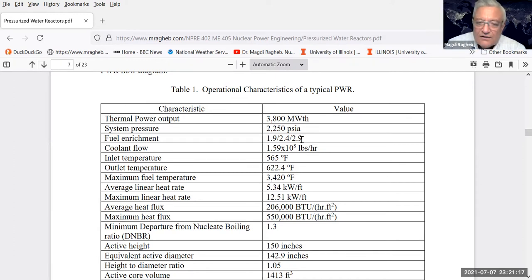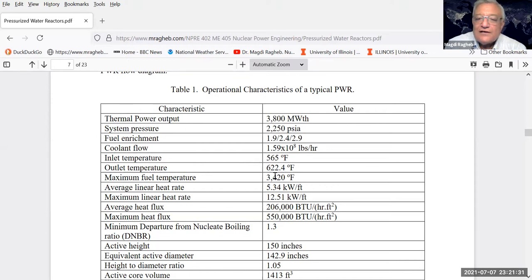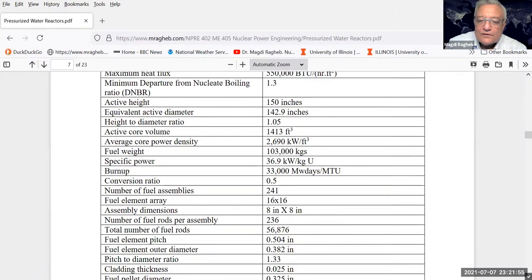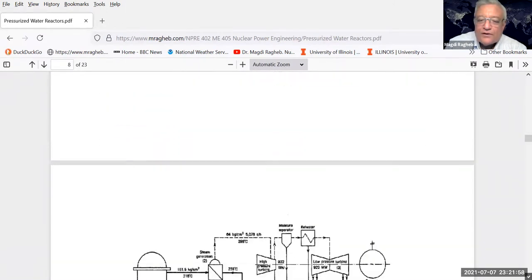This is designated as fuel enrichment. The coolant flow is quite high at 10 to the 8th pounds per hour. The inlet temperature is 565 degrees Fahrenheit and the outlet temperature 622 - only about 60 degrees increase, a rather low temperature of about 350 degrees Celsius. However, the maximum fuel temperature can reach 3,000 degrees Fahrenheit. These are the technical specifications of a typical PWR reactor, which we'll compare later to those of the boiling water reactor.